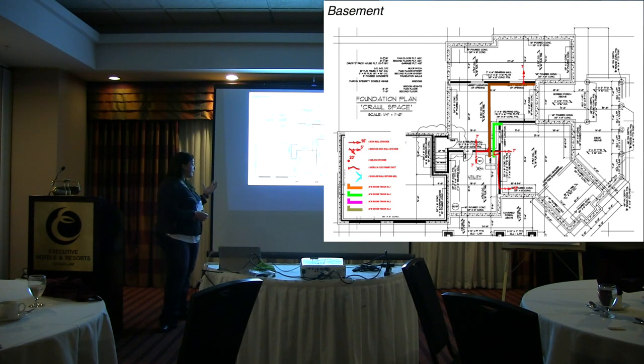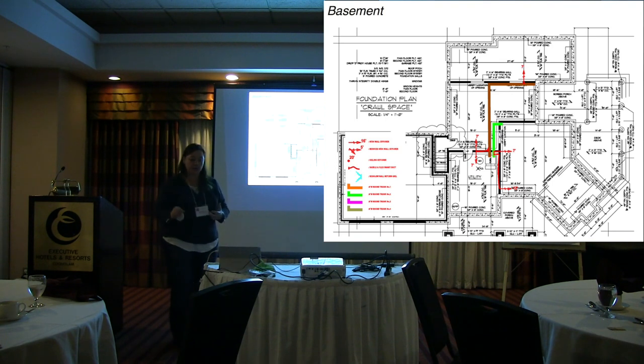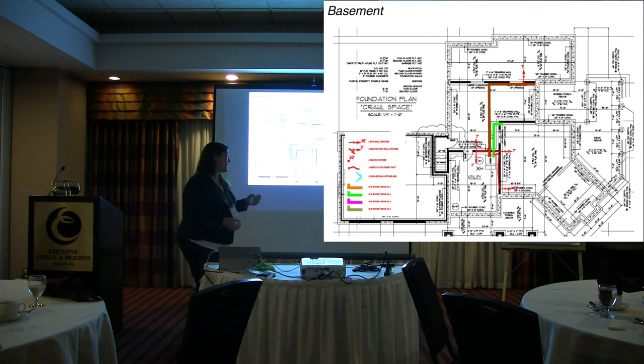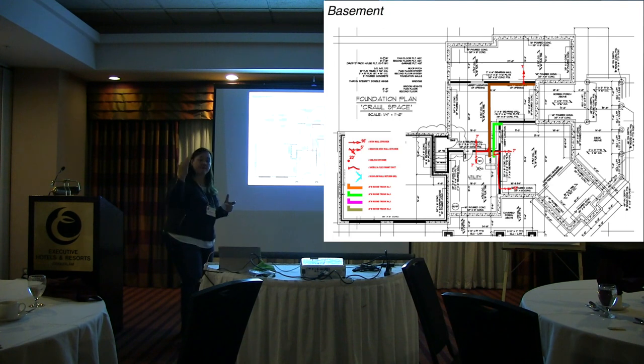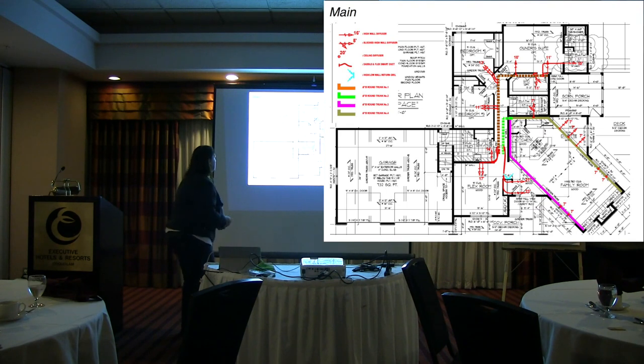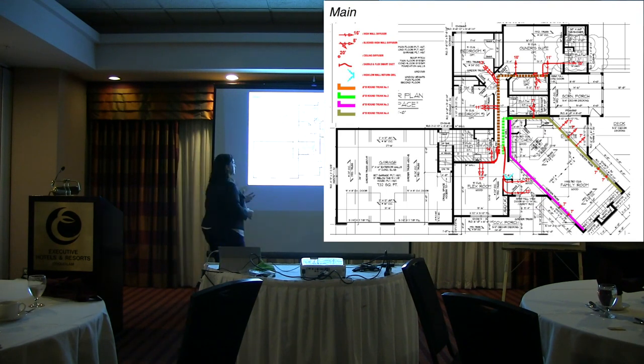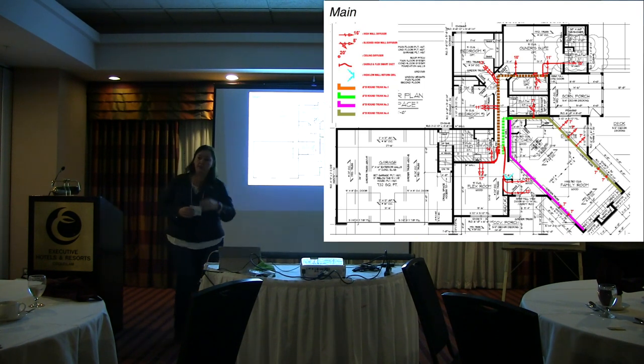And so what we do is, again, take those room by room calculations and help with that. We're helping train HVAC designers, contractors, and distribution to do that duct design. We have some builders doing their own duct design, and engineering firms doing the duct design, identifying where to put the main, centrally located in the house so we can maximize that 25 feet of run to get that house balanced. So the dotted lines, for example, would be those mains in the floor, and the solid, those mains in the ceiling.